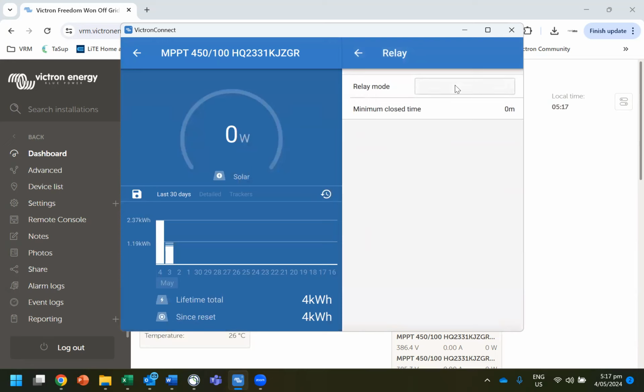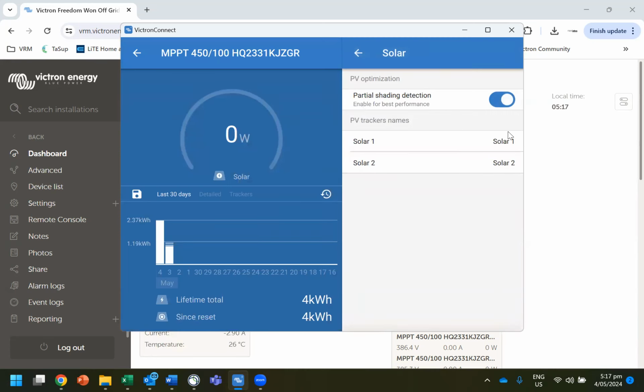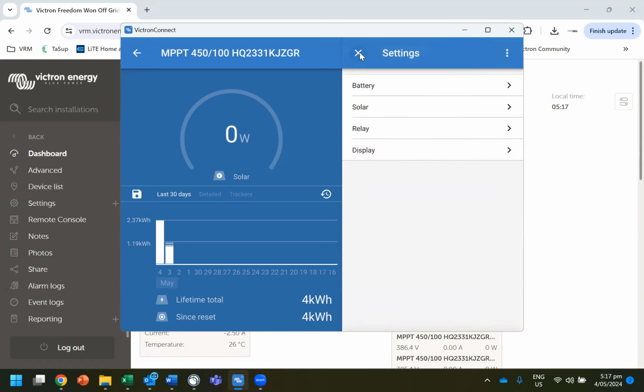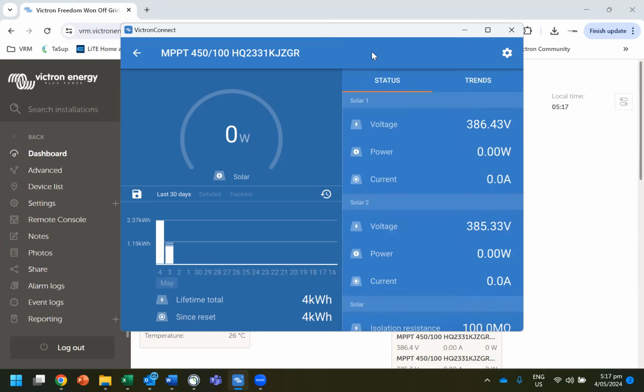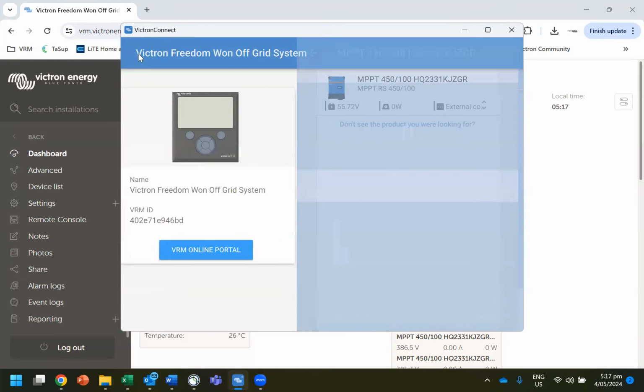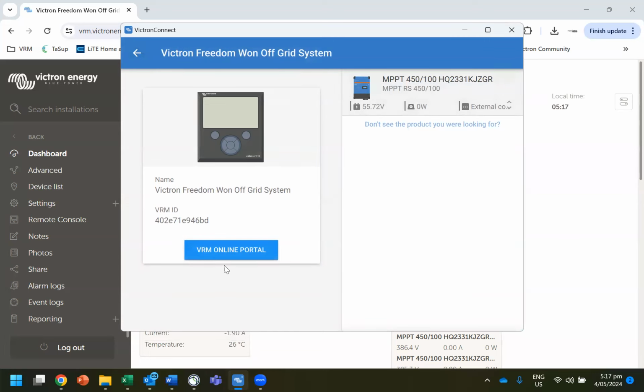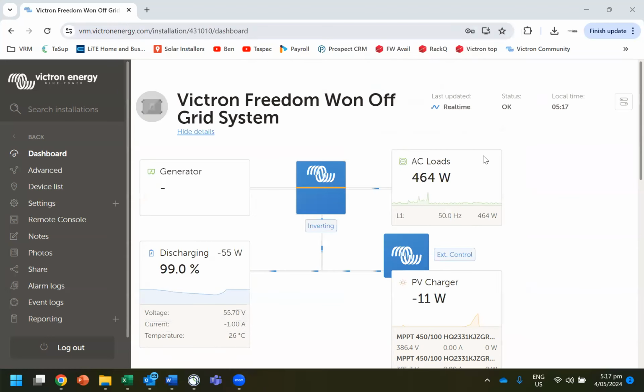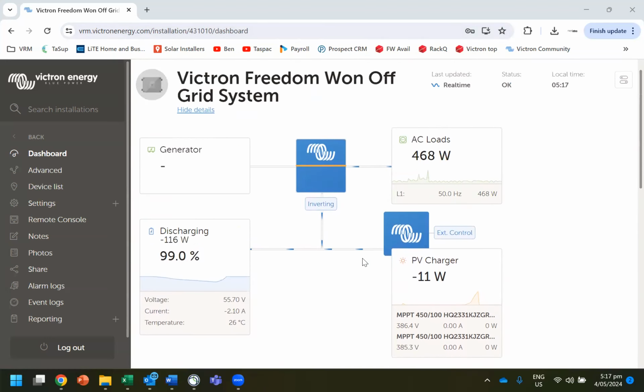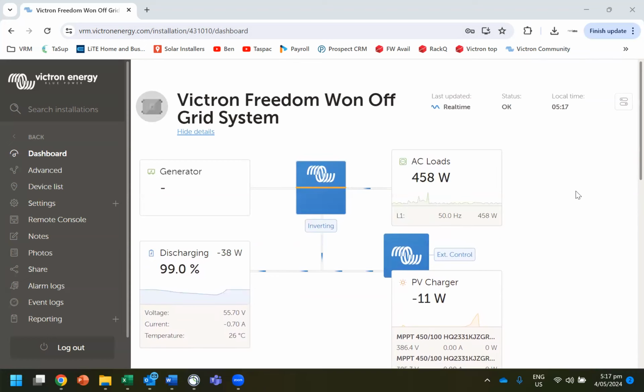You can also program the relays. There's a relay on the device. Basically, leave these at default, really, the other settings. So that's pretty much it. You can close that down, or you can go back. Once you've done that device, you can then go into another device if you've got more than one MPPT, for example. So that is now fully programmed, and you're pretty much good to go.